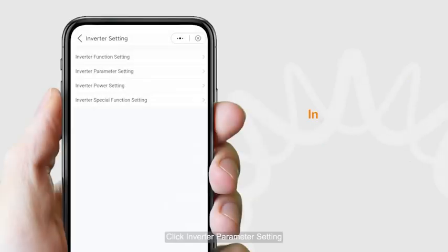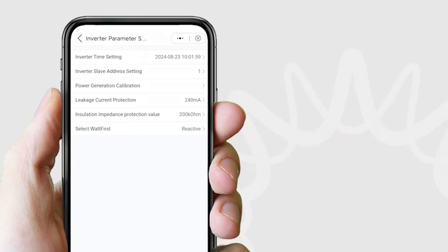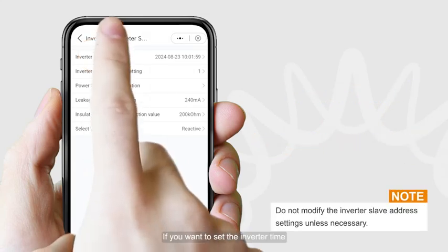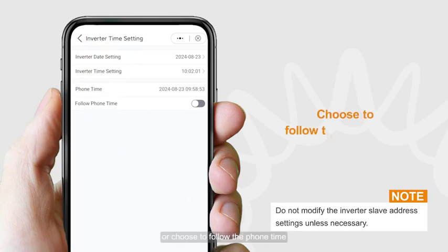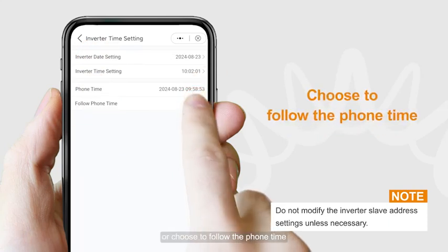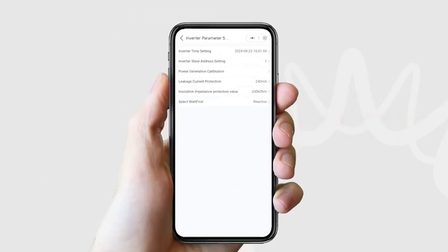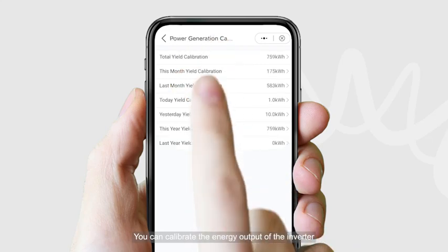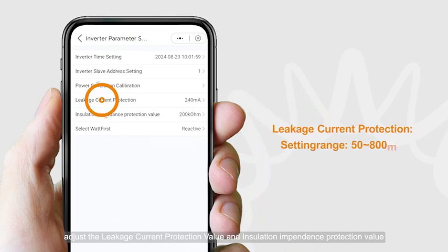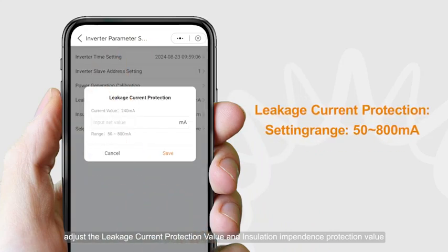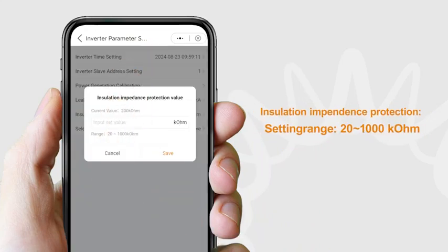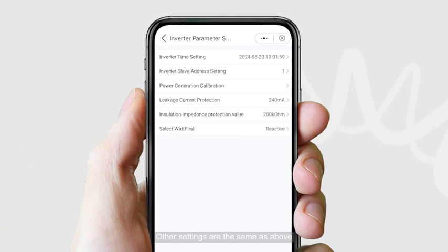For inverter parameter settings, you can adjust any of these options. If you want to set the inverter time, you can manually change the inverter time or choose to follow the phone time. Click Save to confirm your changes. You can also calibrate the energy output of the inverter, adjust the leakage current protection value, and insulation impedance protection value.